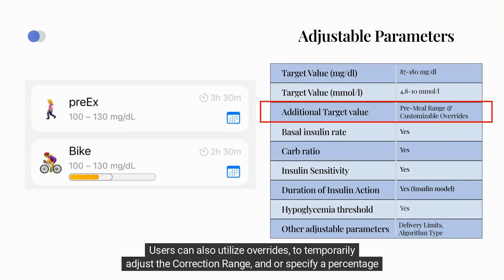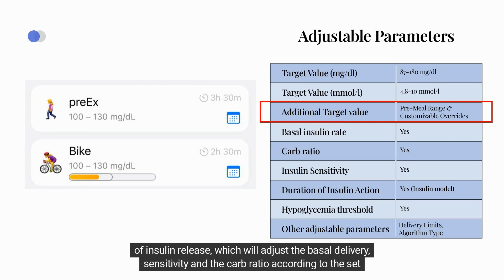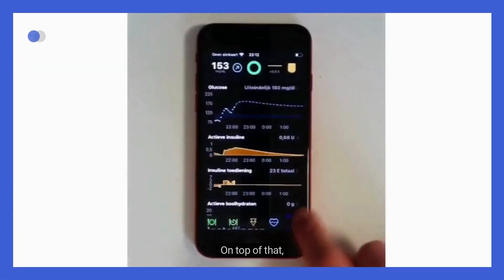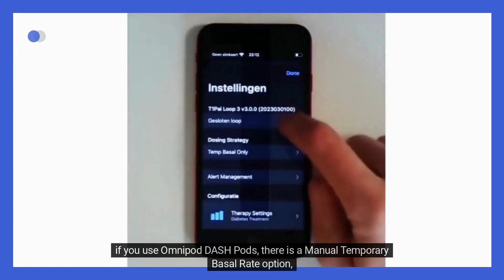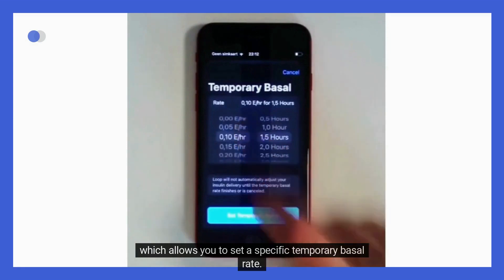Users can utilize overrides to temporarily adjust the correction range and/or specify a percentage of insulin release, which will adjust the basal delivery, sensitivity, and carb ratio according to the set percentage. Additionally, if you use Omnipod DASH Pods, there is a manual temporary basal rate option, which allows you to set a specific temporary basal rate.